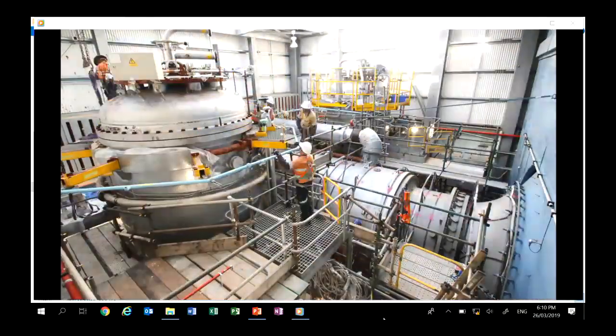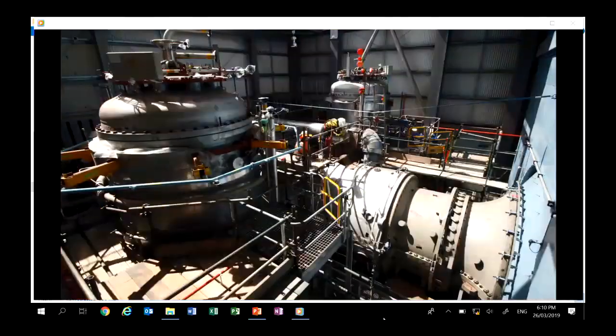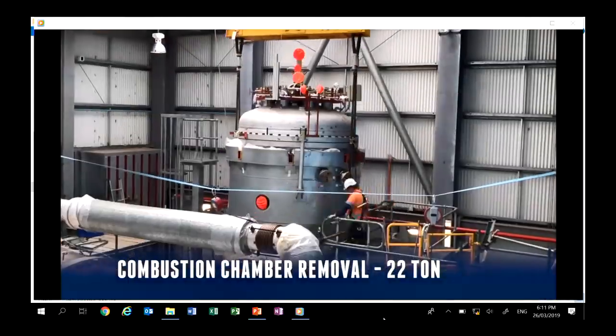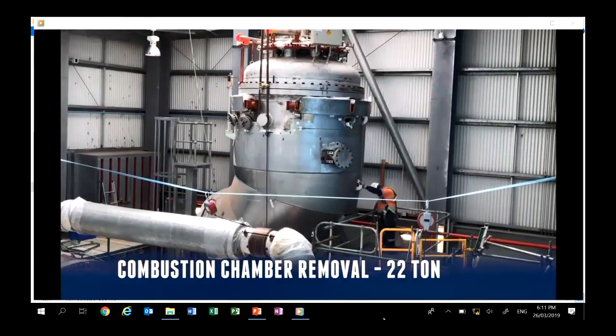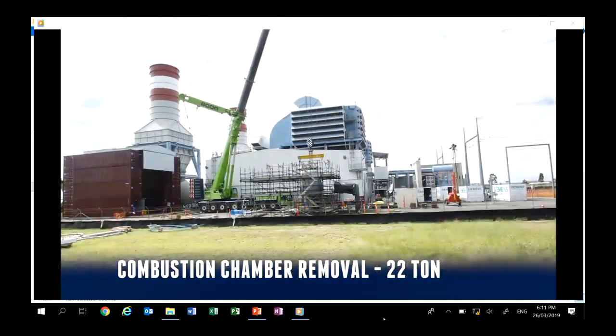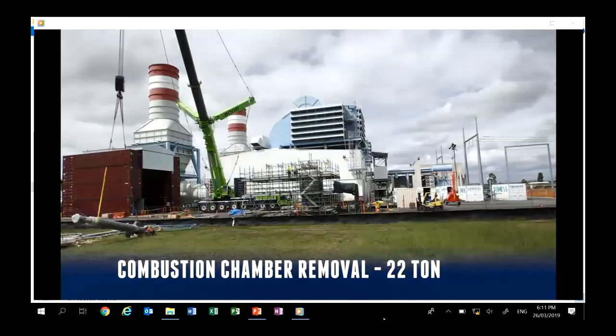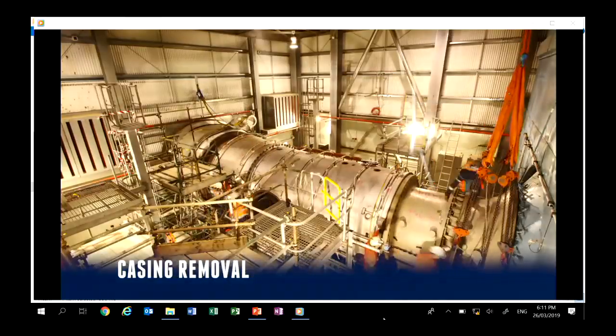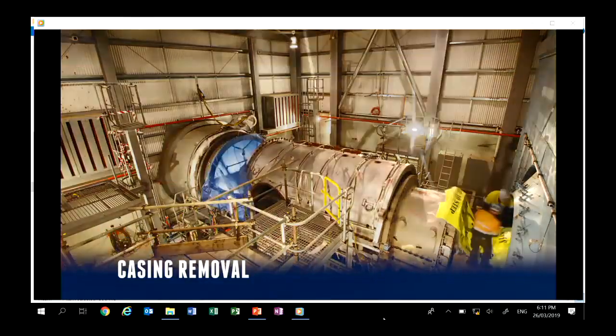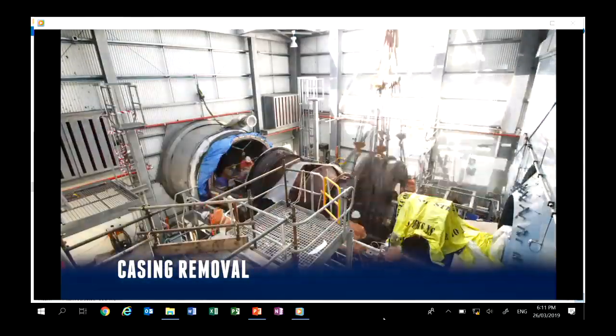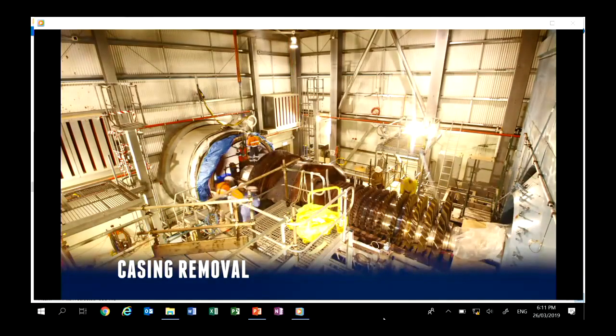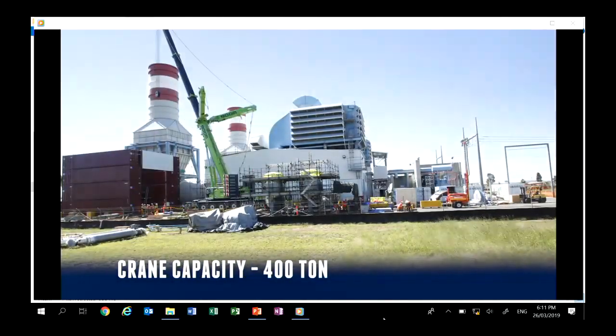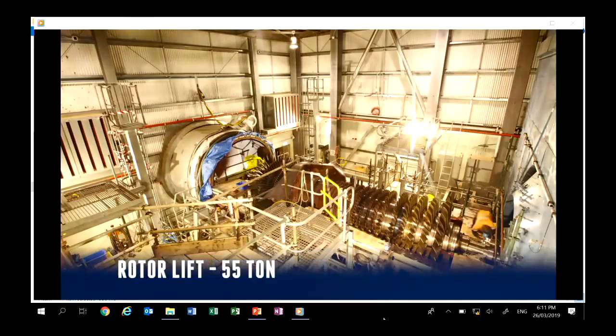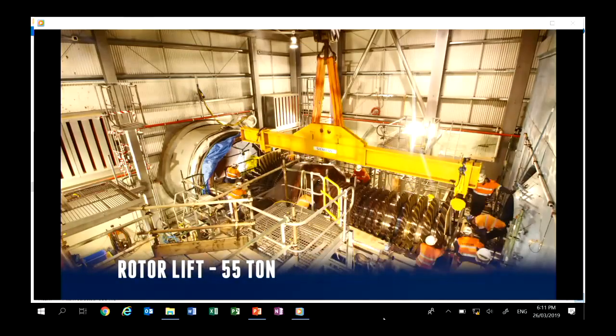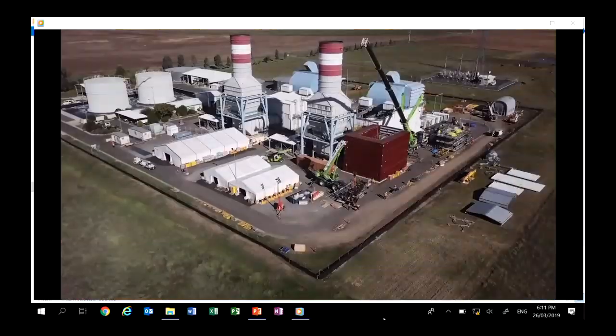So you can see here we're starting to disassemble the gas turbine. This one has 2 very large burner silos either side, so it's a little bit different to the designs we saw earlier. And we actually remove the burner silos. And on a gas turbine, maintenance normally means replacing all of the blades in the turbine, not the compressor, but the turbine where the hot gas is. So in this case, we've got to lift the turbine components out of the turbine house. You can see here the 55-ton rotor is lifted out.